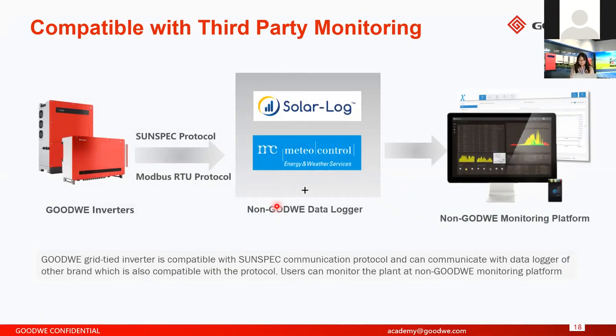So previously, I told you about all the solutions GoodWe provides with GoodWe products and GoodWe platforms. You may wonder, I already have some data loggers. I'm using a non-GoodWe monitoring platform. Can we use GoodWe inverters in the project? Of course, you can. Currently, our inverters support communication compatibility with third-party data logger devices. We have full compatibility with third-party data loggers, and the communication is achieved through the SunSpec protocol and Modbus RTU protocol.